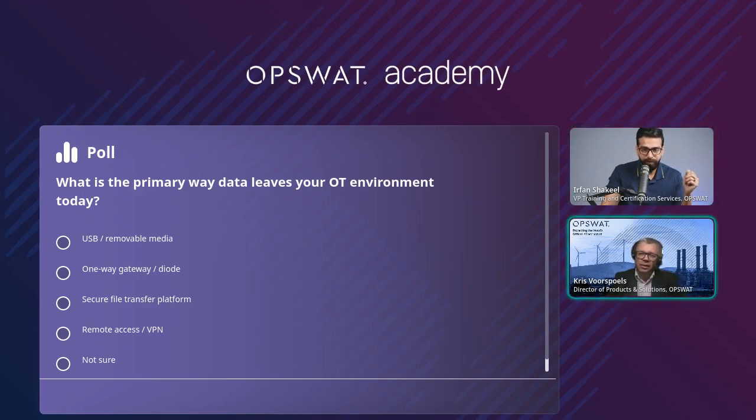Okay, so the truly one-way communication, that's what they call the data diode, right? This is a device which doesn't have any back channel. Typically, they are Common Criteria EAL4+ certified. It comes down to having a physical optical connection from the secure environment to the less secure environment, which is transmit-to-receive only. Not a single bit of data can flow back.